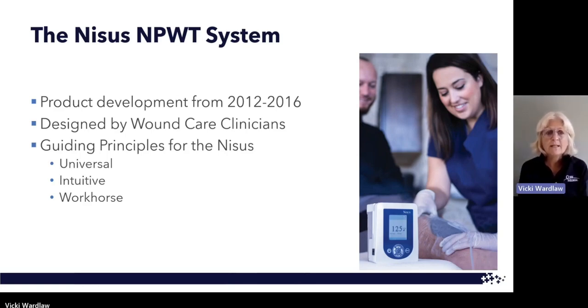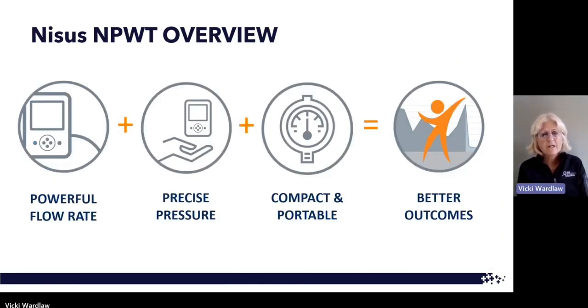We also knew that we needed a workhorse. We needed something that could manage large, heavily exudating wounds, multiple wounds, and in any care setting. So we needed a really strong, powerful, reliable pump. This device, this Nisus negative pressure, has a pump in it that can pull 8 to 10 liters per minute. Typically, what you're looking at using in a post-acute outside of the hospital setting would be about a 4 liter per minute pull.